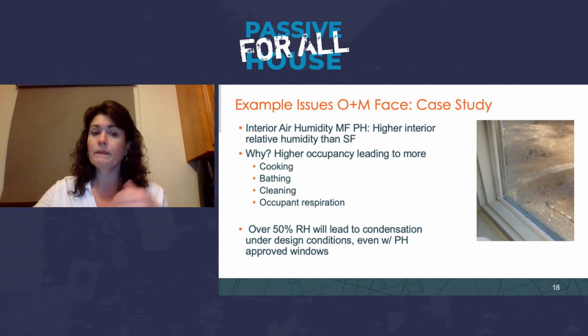So we really need to make sure that O&M staff is aware that these issues can happen and what they can do to help the occupant reduce it. A lot of times we've seen people in apartments with individual ERVs turn their ERVs off. So when we go in, if they're having any kind of high or elevated relative humidity, we explain to them that it will help with these issues. But again, the operation and maintenance staff needs to be able to advise the tenants as well.